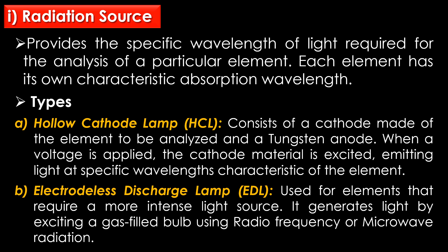The hollow cathode lamp is the most common radiation source. It consists of a cathode made of the element to be analyzed and a tungsten anode. When a voltage is applied, the cathode material is excited, emitting light at specific wavelengths characteristic of the element. The electrodeless discharge lamp is used for elements that require a more intense light source. It generates light by exciting a gas-filled bulb using radio frequency or microwave radiation.